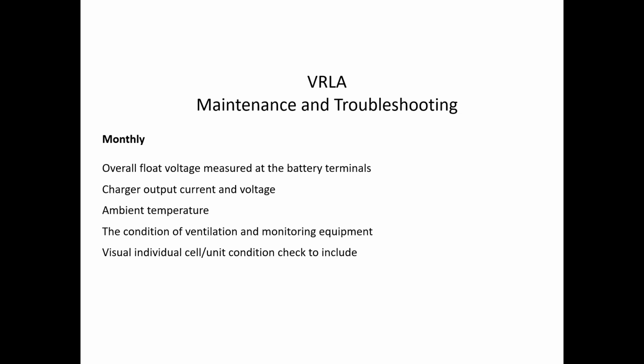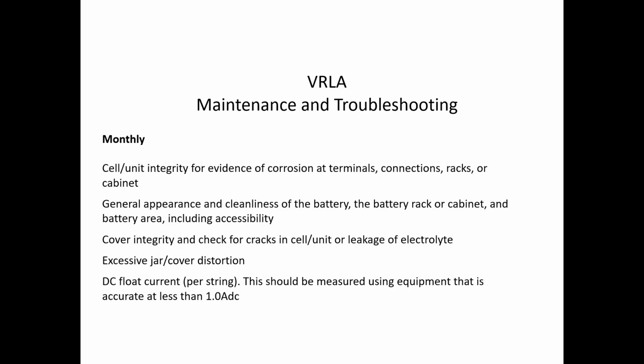If you go through the manual, you'll see that they're recommending monthly routines if possible. Sometimes that's a luxury. Everyone's stretched thin for manpower or technician availability, but check overall voltage, compare that against the charger output, looking again for any kind of drop. Ambient temperature too. I'm not going to read everything, but the monthly is pretty much just a walkthrough, make sure flames aren't shooting out of the rectifier or out of the battery. So a visual is really what the monthly turns out to be. It's not a bad idea.